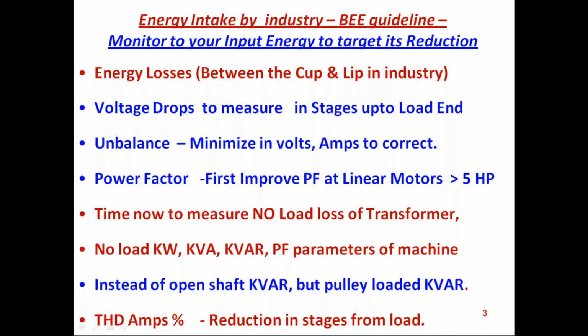Coming to the machines, whether it is a motor or a pump or a blower or a compressor, we need to know what is the tare load consumption for the given machine without loading, and with loading what is the consumption. This will be kept on record. This will automatically give us an input where we are maintaining the parameters, optimizing the parameters. Instead of having an open shaft kVAr, if the machine or the motor is loaded with the pulley and the kVAr is monitored, there we can definitely have the inputs of the kVAr, that is the no load kVAr for the given system.